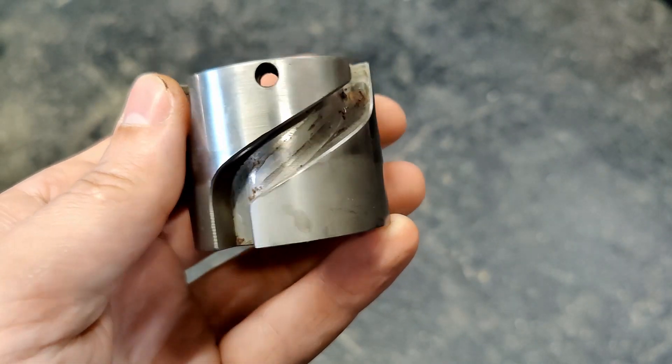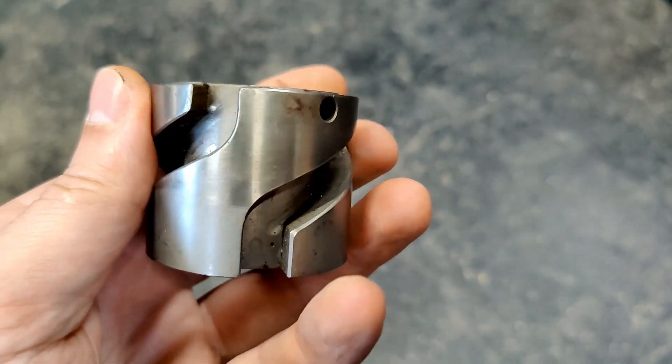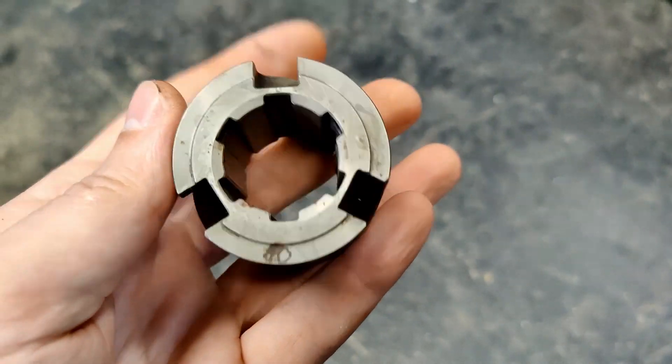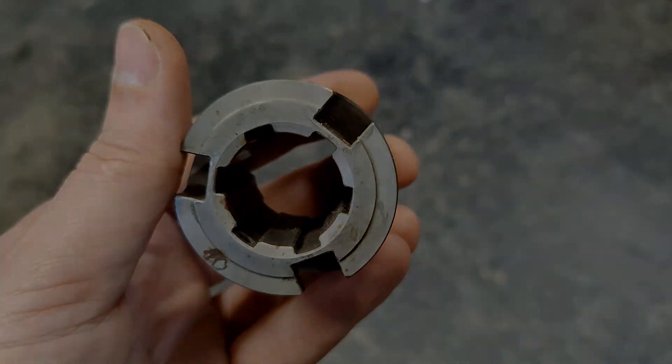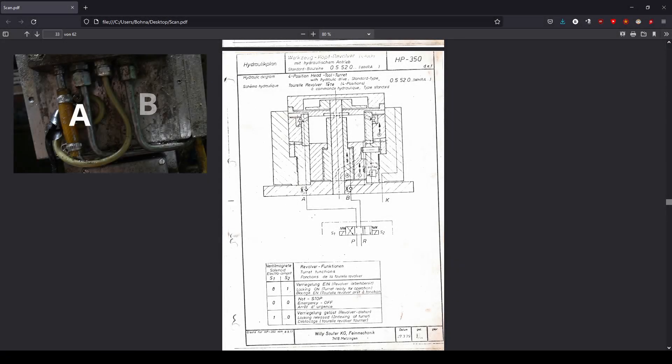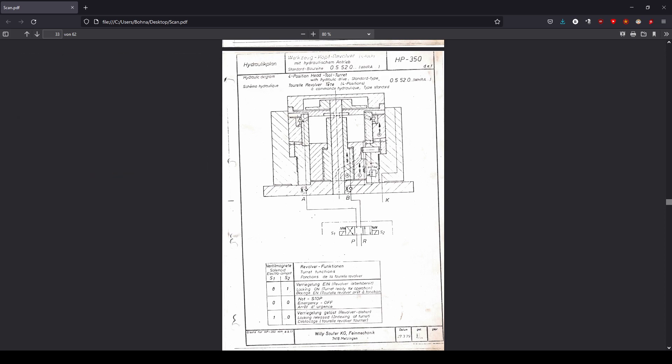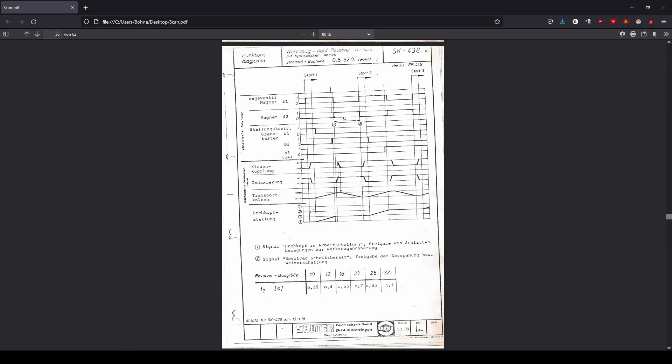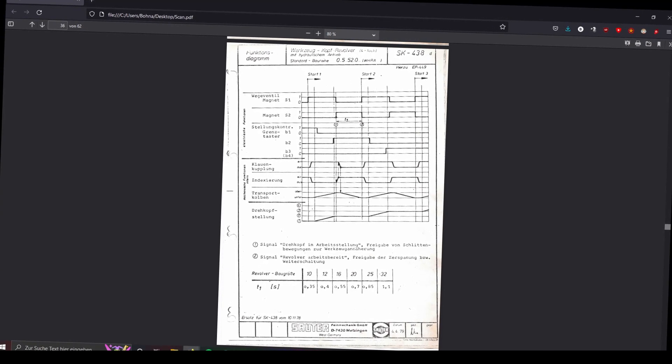In the middle there is a piston, which looks like this. This is moved by hydraulic pressure. The whole thing can be seen in more detail here. We have a port A and port B. These are connected by two hoses to two solenoid valves, S1 and S2 at the hydraulic aggregate. Here below is a table of how the solenoids are switched to use the turret. When S1 is off and S2 is on, the turret is blocked and ready for operation. If S1 is on and S2 is off, the turret will be unlocked and the working piston will move upwards, turning the turret once by 90 degrees. Otherwise, it is still described here as an emergency stop when both are off. I think this traps the hydraulic oil in the turret and nothing moves. Here is also a table of the switching times and the expected sensor data.